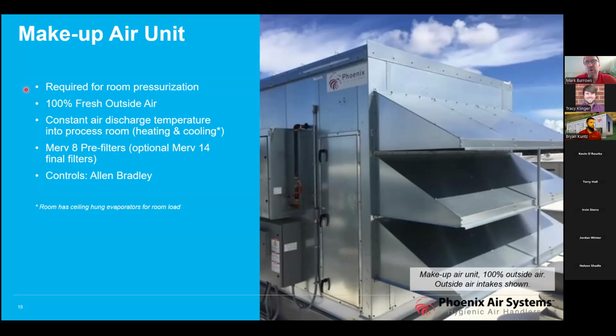No cooling, just raw ambient air. If it's cold outside, the burner would fire off. Again, since you're bringing in outside air, you'd have to have at least a MERV 8 pre-filter. A lot of guys like to use a MERV 14 in the discharge just to make sure whatever they do bring in is certainly cleaner than that of the room itself. Same control strategy with the Allen Bradley control platform.